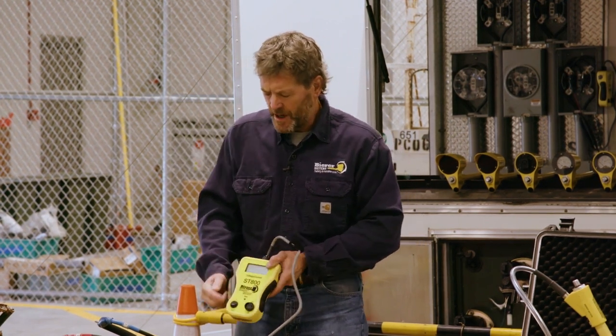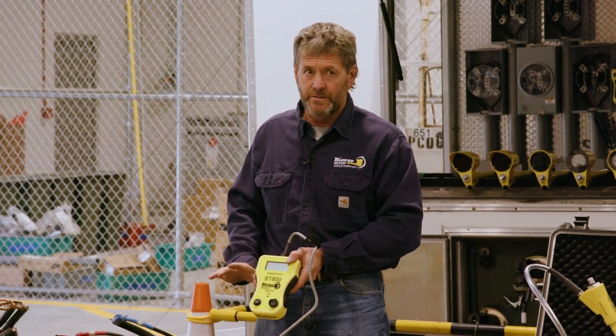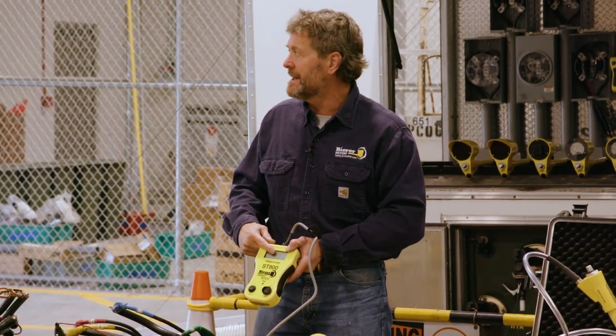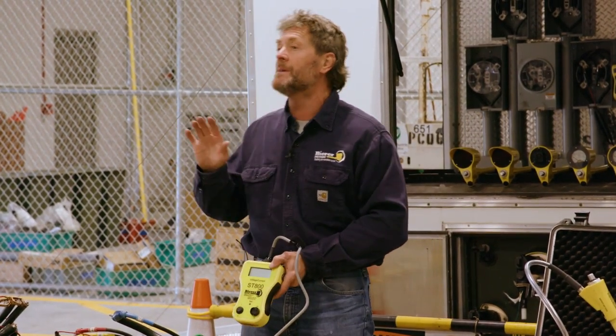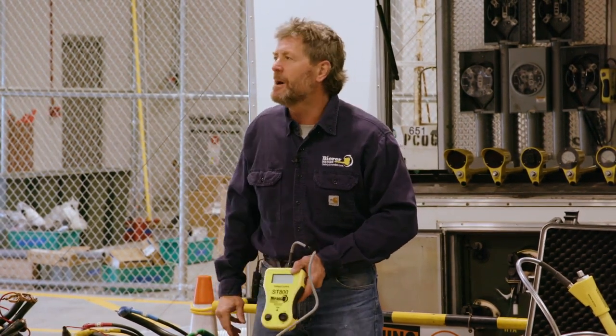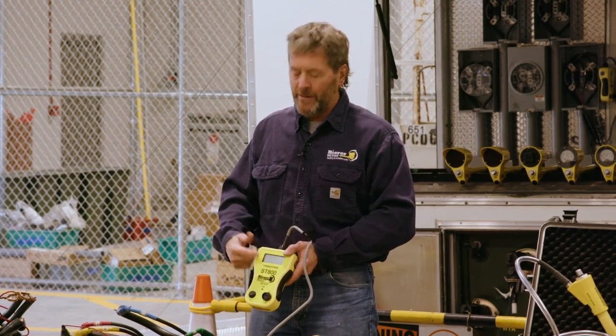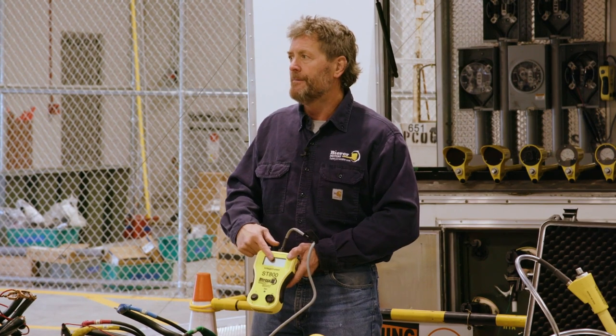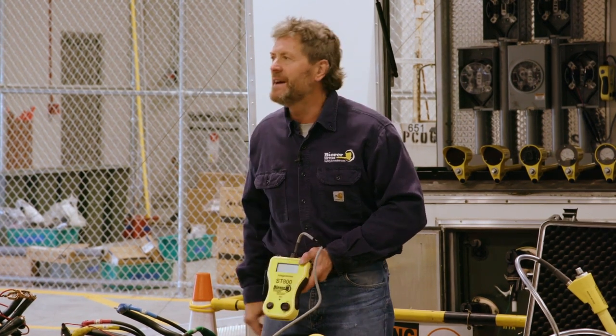Then you're gonna toggle from the voltage to the load, and it's gonna sequence the count. You'll see the count and the load climb up. But because you saw 100 volts, you know the load climb is gonna be very slow because the integrity is bad. Sure enough, you're seeing a 2 amp jump each count. It sequences the count on the screen to the load. It gets up to 40 amps, falls on its face, and starts recounting. You've got a splice, or a lot of lift poles, and you hear a popping sound over yonder. So the tool, because it's in the clear, has already found the issue for you.